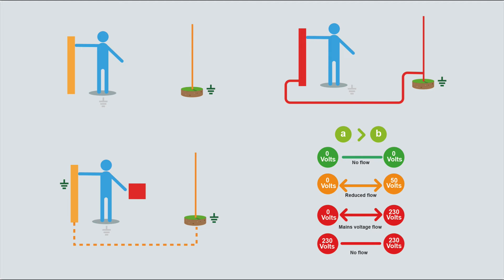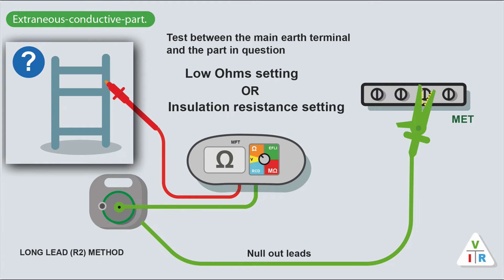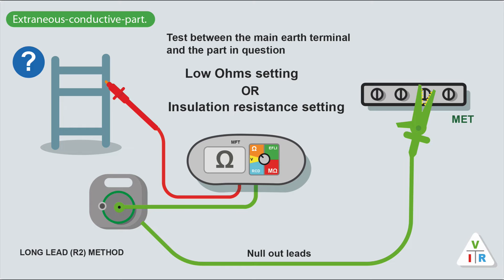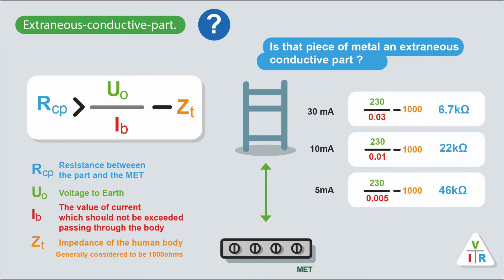So to test and make sure that something is not an extraneous conductive part, we need to get our multi-function tester and test between that part and the main earthing terminal. These can be quite a long distance apart - the bundle lead, or long lead, R2 lead, whatever you call it, is useful for this. Don't forget to null the leads out. We connect one end to the MET and then with the low ohms setting we test the piece of metal to see if it's extraneous or not. You can use the low ohms setting or you could use the insulation resistance setting, only if your meter doesn't have the resolution that you need. Most modern meters now have a normal resolution - mine has a resolution of 99.9 kilo-ohms. A few years back you didn't have that, so you had to use the insulation resistance setting. So we test between the MET and the piece of metal and we get a reading.